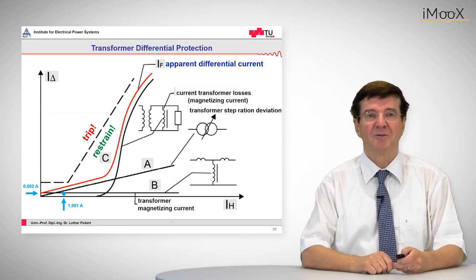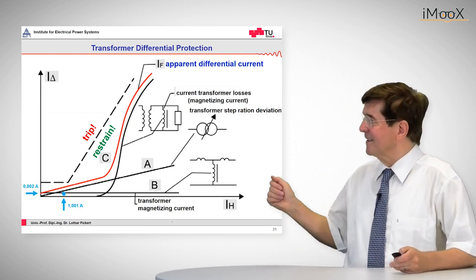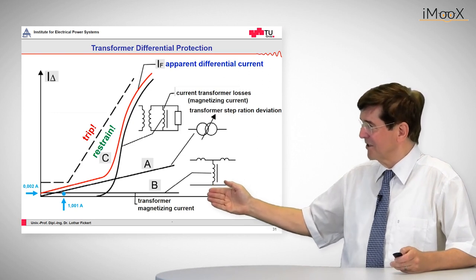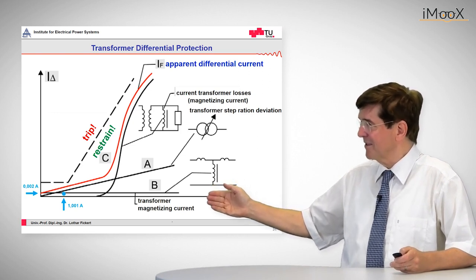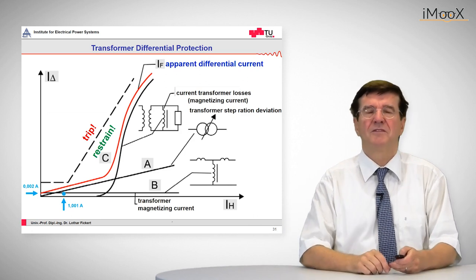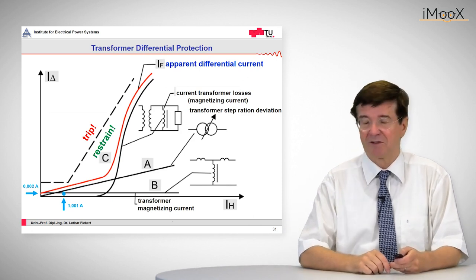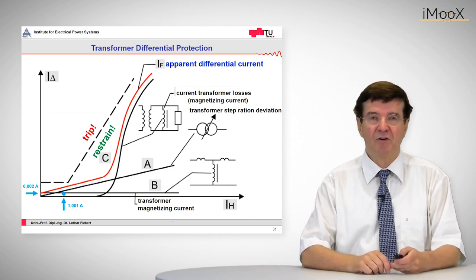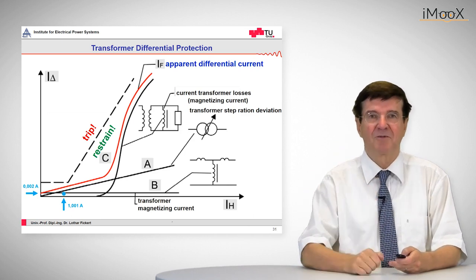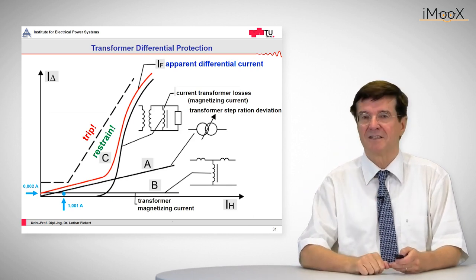In order to demonstrate this, I go back to the example of the magnetizing current of the transformer that we have seen before. So we have here the stabilizing current which is 1.001 amps and a very small differential current of 0.002, and as we can see, the blue dot is below the trip curve and the protection is stable.